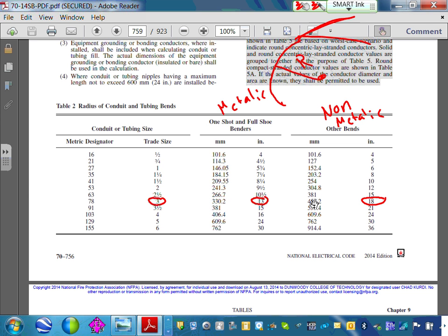When you bend, there are rules, guys. When you are bending in the machines that we have here, one shot, you can decide the radius for the bends. How do you figure out, say, the trick method? Have the EMT, and it says the radius is 4. How do you measure that on the EMT? Oh, you go by the trade size. Yeah. How do you take the EMT that's already bent and make sure it's 4 inches?